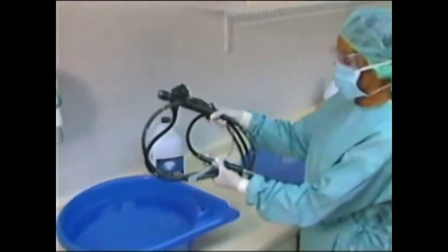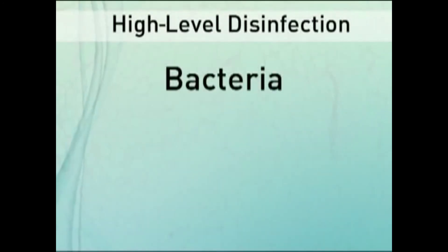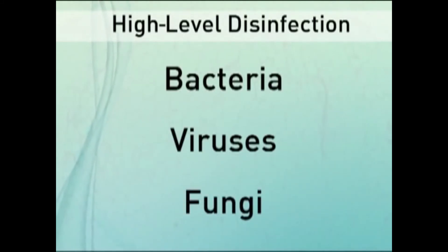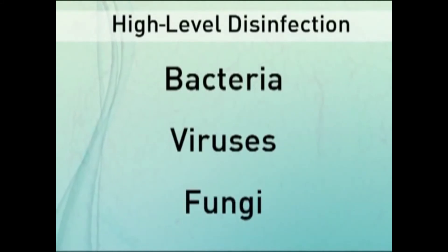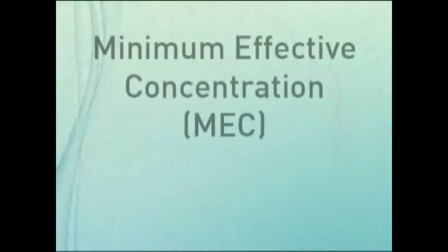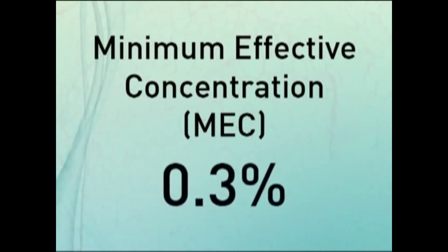High-level disinfection destroys microbial activity of bacteria, including TB, viruses such as HIV, and all fungi. The MEC of the solution may be verified by Cidex OPA solution test strips. The MEC of the solution is 0.3%.